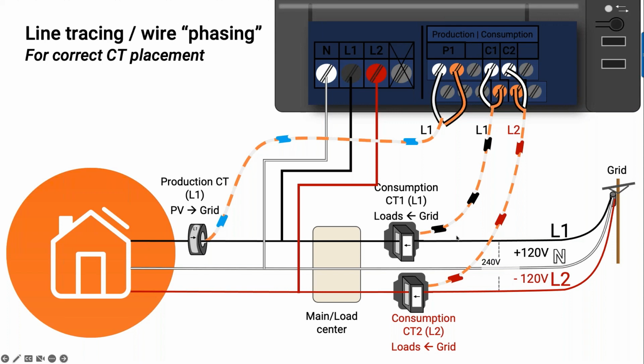Now, what happens is that if you miswire the CTs, like you cross these wires or you mix up line 1 and line 2, you're going to get inaccurate readings. One of the ways installers are not catching this is phase errors. That's when you're measuring voltage from one phase, so maybe voltage from line 1, and then you're getting current from line 2. There are times when homes actually have wires that are crossed.